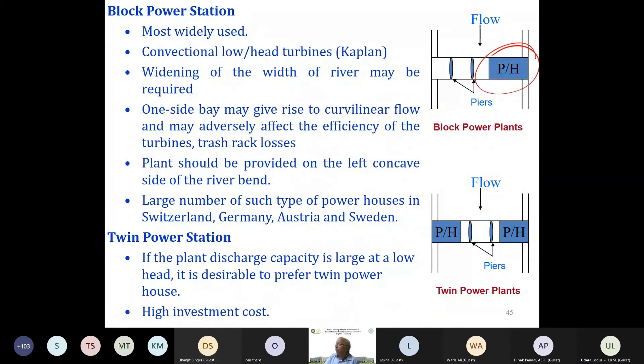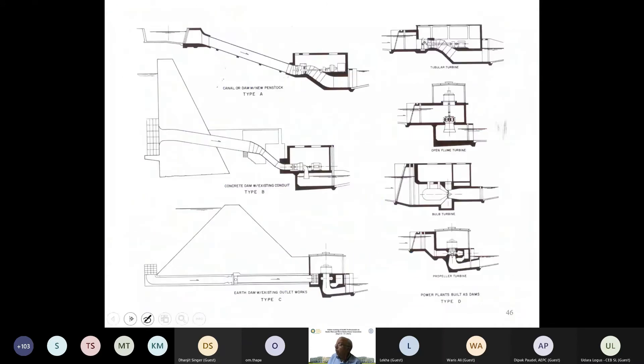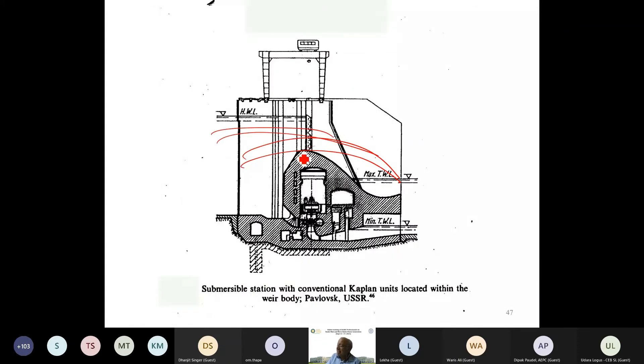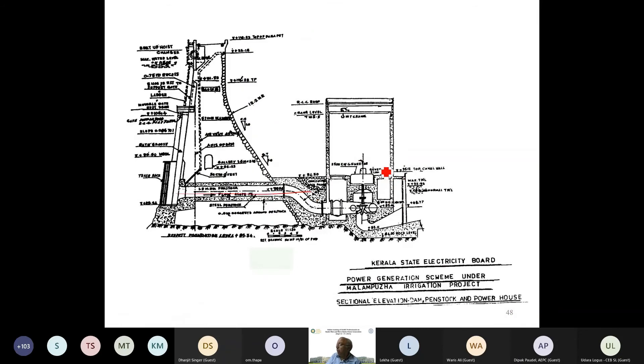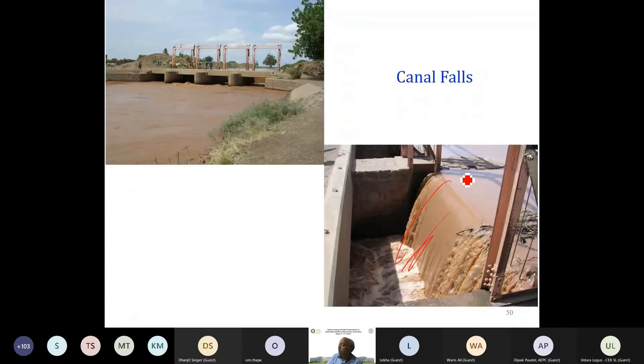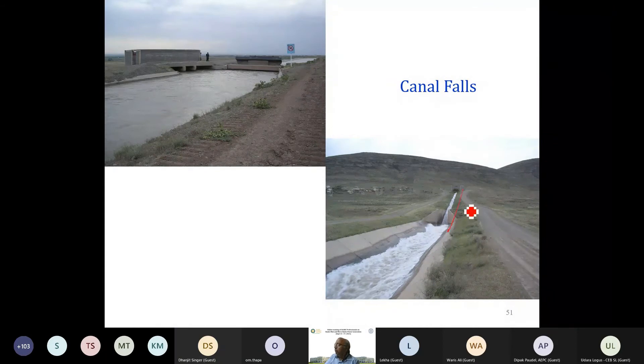For existing dams, you can have a powerhouse inside a weir, or different machine configurations. Overflow-type projects were constructed in Eastern Europe in the 1950s and 1960s and are no longer common but remain technically possible. A siphon mode installation is also possible — where water flowing over a fall can be taken by siphon and a turbine installed. For example, a 20-meter fall with 5 cubic meters per second: why not develop it?